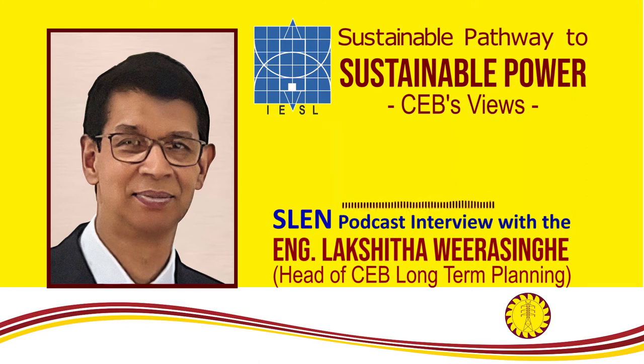That means when the mechanical inertia of all the generators is high, there is a lot of kinetic energy, and that kinetic energy can take care of sizable supply-demand imbalance without causing a significant change to the speed or frequency. But when the mechanical inertia is low, there is a higher change to the speed required to give the same kinetic energy, and as a result the frequency can be affected.